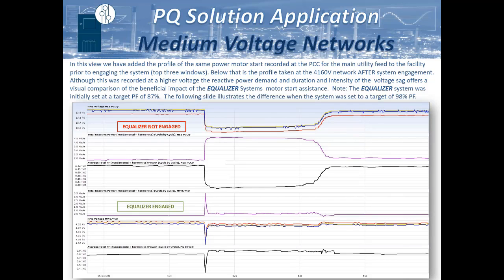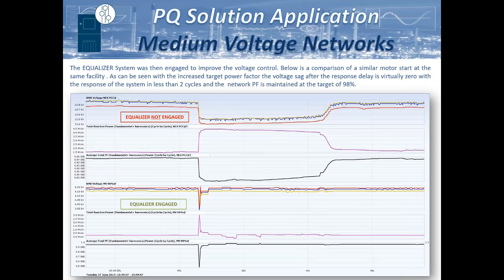So then we actually compared, we had multiple meters, one on the utility side of the 13.8, as well as downstream. And you can see that we've compared the previous baseline measurement upstream to once the system was engaged. You can see that even had quite a significant impact on the 13.8 side, which is being seen throughout the operation, even on the low voltage side of the facility. When we set it to target power factor 98, you can see we even shortened this and added even greater stability to the network.